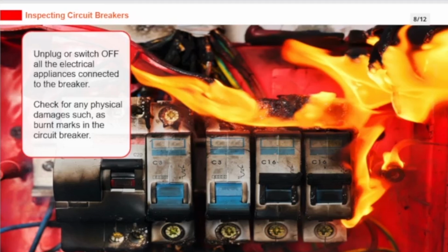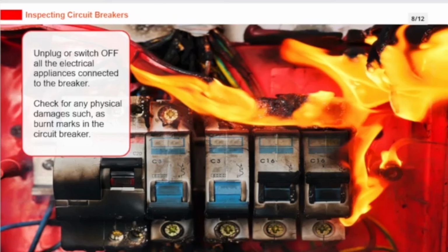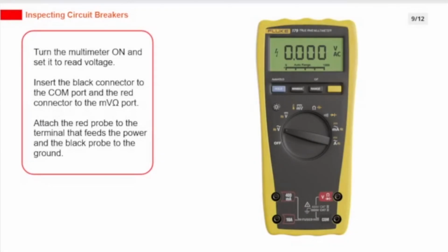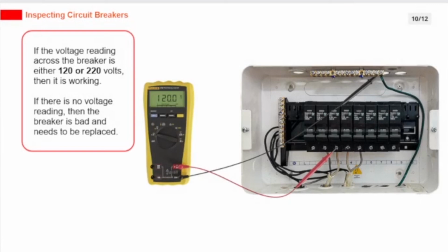Unplug or switch off all the electrical appliances connected to the breaker. Check for any physical damages such as burnt marks in the circuit breaker. Turn the multimeter on and set it to read voltage. Insert the black connector to the COM port and the red connector to the V omega port. Attach the red probe to the terminal that feeds the power and the black probe to the ground. If the voltage reading across the breaker is either 120 or 220 volts, then it is working. If there is no voltage reading, then the breaker is bad and needs to be replaced.